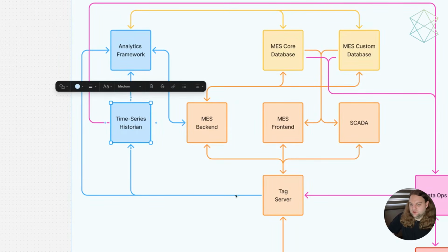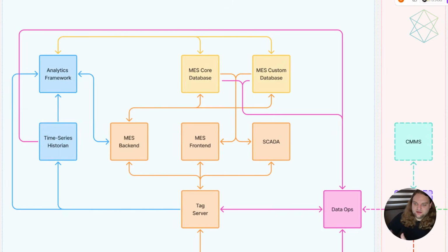That process historian, it's all of our telemetry, our scalar data, it's all of your instrumentation readings, it's all of your in-flight just streamed telemetry. So that will be every time you get a new temperature reading, it's going to log it to that. Every time you get a new pressure, a spindle speed, an amperage, all of that's going right into that time series database, the historian, Timebase. And that is in here as a time series data store, as a stream of telemetry data.